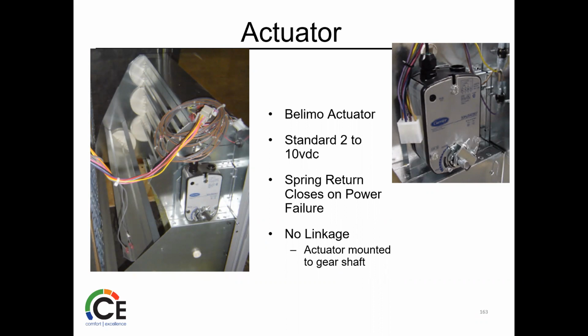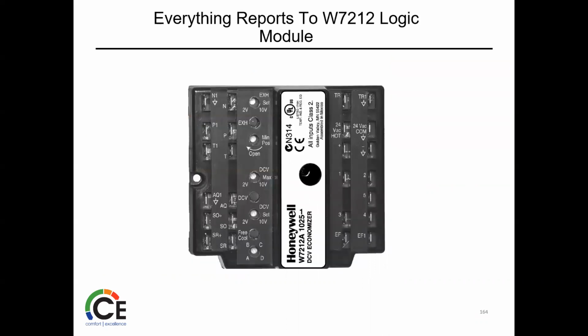Standard 2 to 10 volts. So again, when we're testing, we're looking for DC voltage. This one is a spring return, closes on power failure. There's no linkage or anything really overly complicated in there. Everything reports here. So we've got sensors out there, whatever wiring, it all comes here. So whatever that system wants, when the signals come through, it's coming here. Low voltage side and controls on the right, settings and supply thermistors on the left.